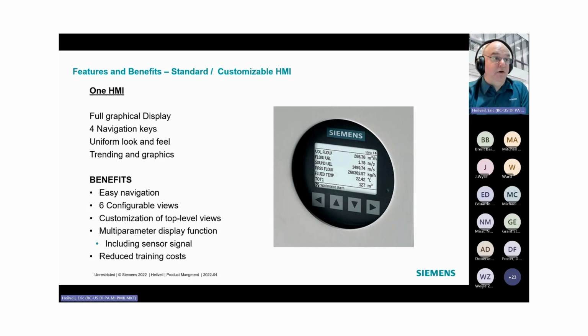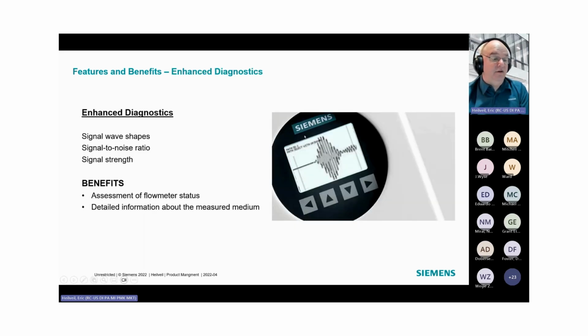So this becomes a critical part of troubleshooting. If there's a problem, you can actually get the sound wave diagnostics directly on the display. And the benefit of that is that if your transducers get knocked, or if you start losing signal, or perhaps you're getting a high degree of aeration because of a hole in a pipe or a leaky packing on a valve, you can use this type of tool to help identify what the problem is.